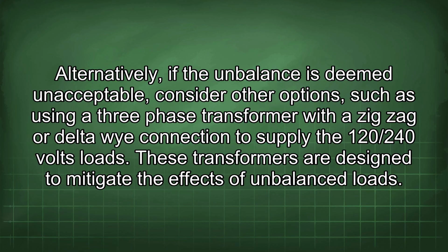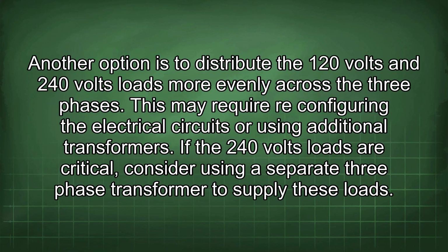to supply the 120/240-volt loads. These transformers are designed to mitigate the effects of unbalanced loads. Another option is to distribute the 120-volt and 240-volt loads more evenly across the three phases. This may require reconfiguring the electrical circuits or using additional transformers.